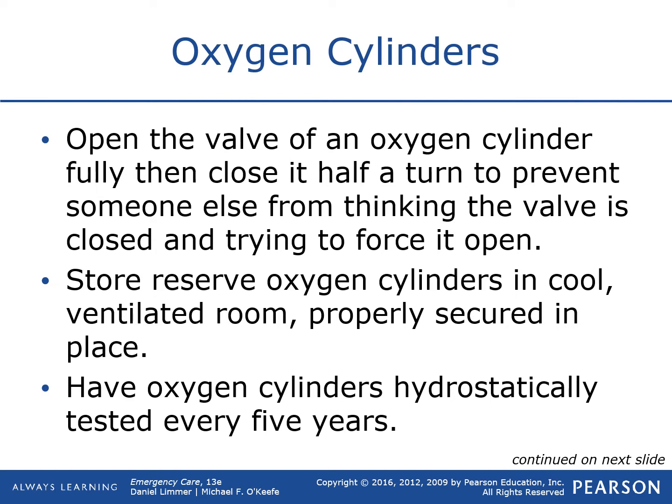That way, if someone comes after you and they think that they need to open up the oxygen tank, they don't turn into the fully open position and think that it's either one, that it's broken, they need to try to keep on shoving it that way to open up, or two, they think that they're closing it since they hit resistance, so then they go to what they think is open it and it's actually closing it all the way. So as you go just a half turn back, then it's going to be most of the way open, but it'll still have play on both sides so that someone else will know that it's open.